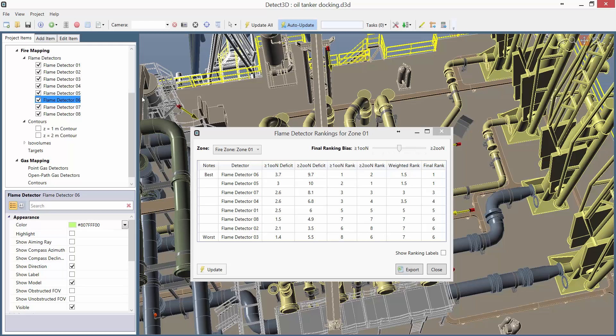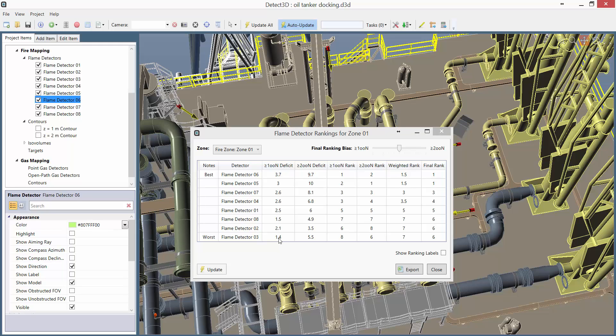If you think about that process, any detector that you switch off and it doesn't affect the coverage that much is a poorly placed detector. We can see the exact results of that process here in the detector ranking window. Each row is for one detector. Next to the detector we can see the 1 out of n deficit, that is how much the 1 out of n coverage was reduced by when this detector was switched off.